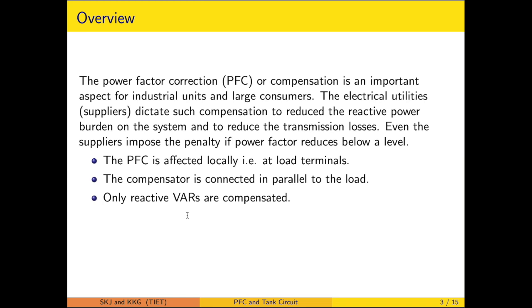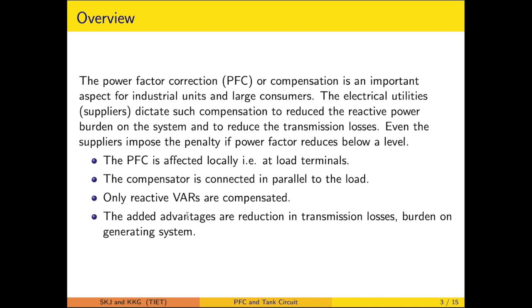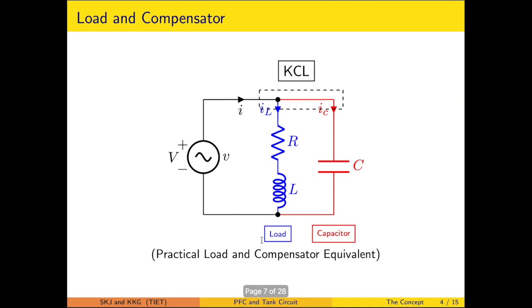The point to be considered is that if the load is of inductive nature, then the compensator has to be capacitive, and when the load is of capacitive nature, then the compensator has to be of inductive nature. Now as mentioned, the outcome of this compensation is a reduction in the transmission losses and the burden on the generating system.